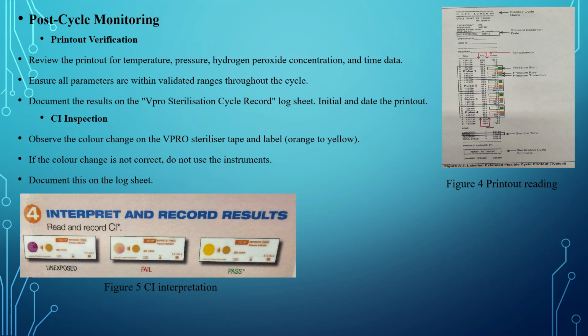Post-cycle monitoring. Here we are monitoring the printout verifications. We have to look at the printout, the temperature, the pressure, the hydrogen peroxide concentration, and the time and date at which the cycle was started. By doing that, we ensure all parameters are within validated range throughout the cycle. If it goes up and down, that means there are some issues, and it is possible that it will fail the cycle. So document the result on the VPRO sterilization cycle record log sheets, initial and date the printout.